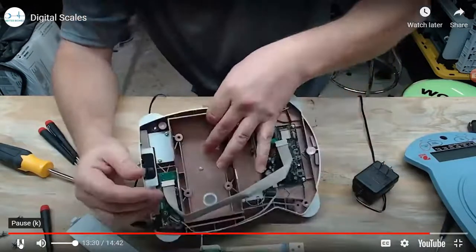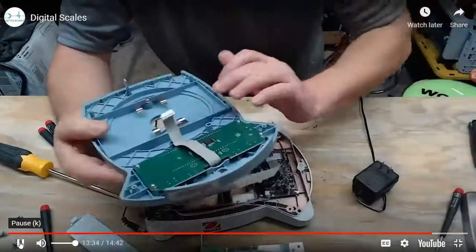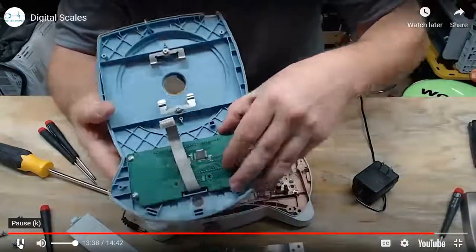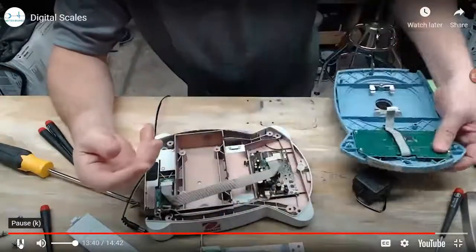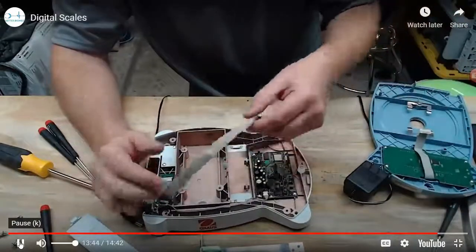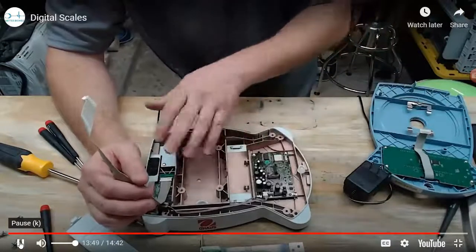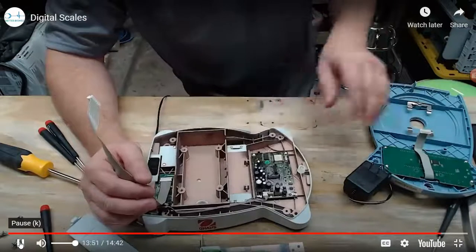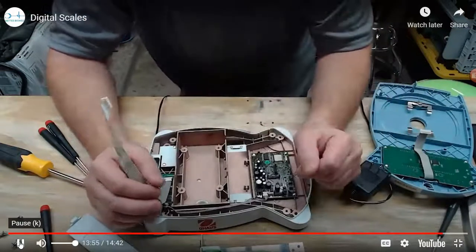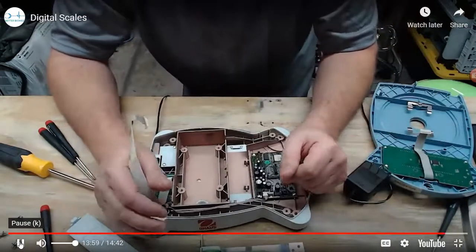So that is the digital scale. Nothing too fancy. Up here, you've got your membrane buttons, which go to your controller for the membrane buttons. And all they do is relay back to your processor. So the processor is doing the comparison of your load cell on the Wheatstone bridge, and it's also taking your commands from the membrane buttons. Pretty simple. Nothing major there.